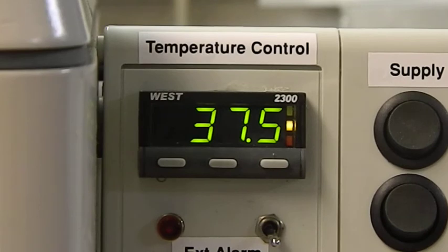What I'll do is I'll read quickly through the parameters so they've got a complete list of them. In the first settings, which you get into by pressing the right and left buttons together and holding them, once it flashes you press the center button. The first parameter is SENS and the value is 810. Then RLO 0, RHI 40, OUTS 0.210 or 0.212 for the USB versions, SPS 1, AL1T DER, CNTL R-P, and TUNE MAN.